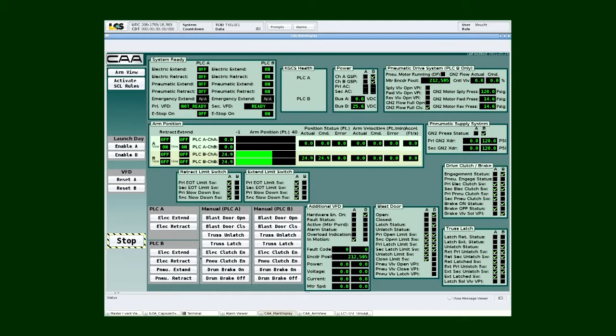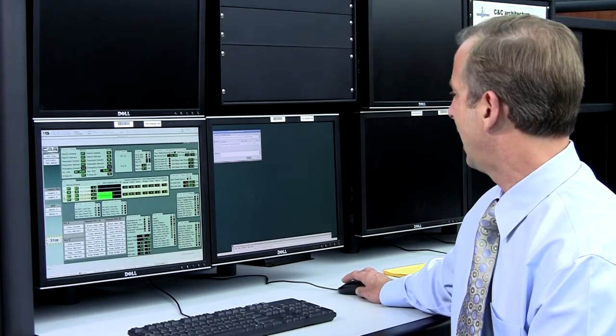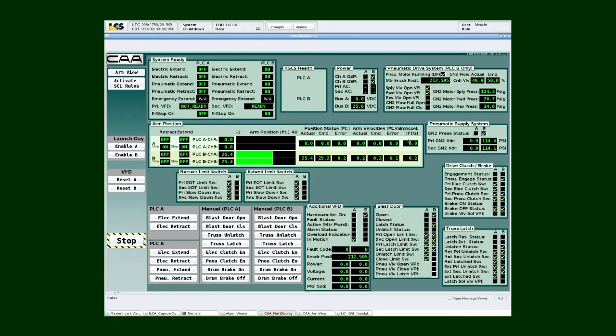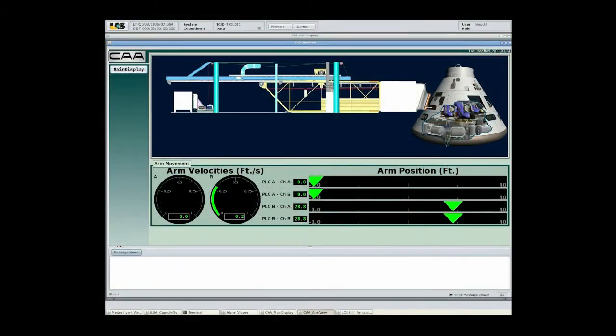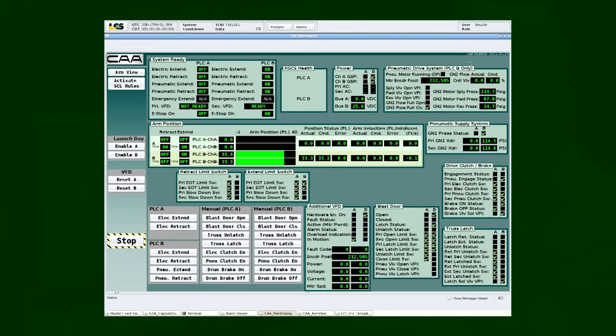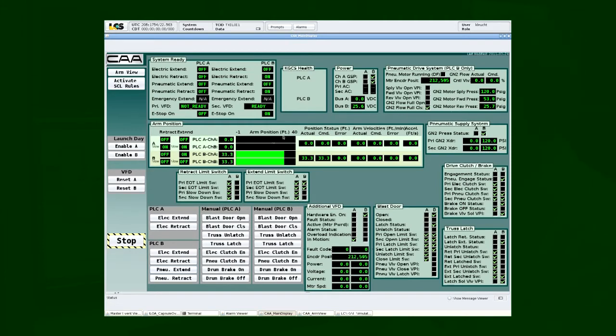So I'm going to go ahead and select pneumatic extend, arm my command, and send my command. And if you notice and take a look at our screen, we do notice that the drive and clutch mechanism switches from electric to pneumatic, our brake released, and now we're continuing motion on our pneumatic drive only in the extended direction. My current position is about 30 feet. And of course if you look at the information for the pneumatic motor, you can see that we do have forward pressure matching supply pressure. Once my arm reaches its near fully extended position, it will hit a set of slowdown switches, which prompt the system to respond by reducing the pneumatic drive motor, which decelerates the arm and brings it to a slow stop. Once the arm is detected at the fully extended position by the limit switches, we de-energize the nitrogen supply valve to the motor, and the motor pressure will drop off and we will stop at our current position, which is 33.3 feet.